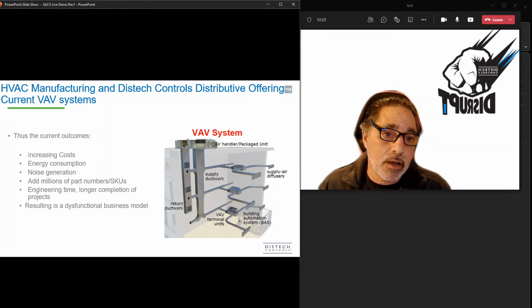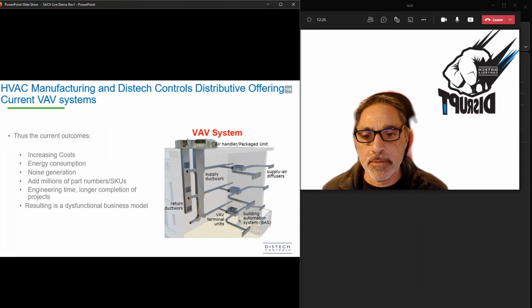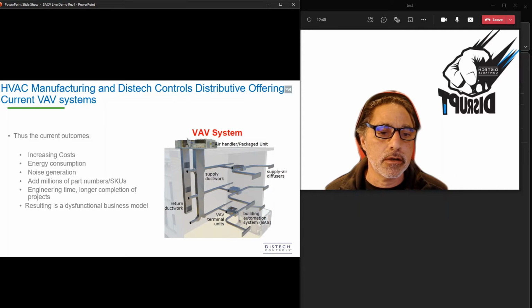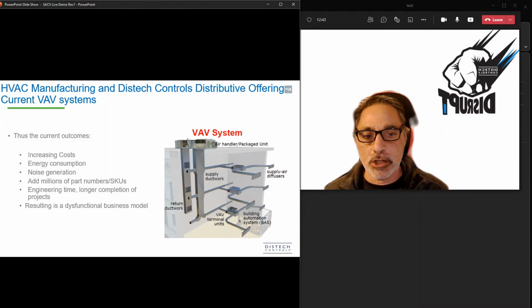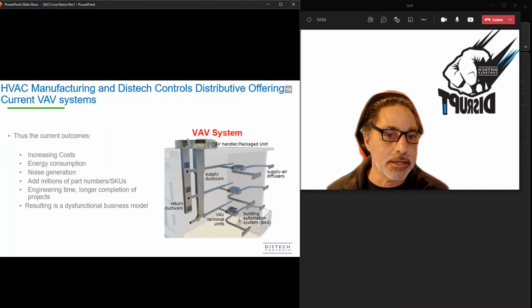And one thing that I haven't really mentioned even on the slide here: when you install a VAV system, what happens if a retrofit happens for that owner who wants to maybe move the walls around, change the design? What happens today is you almost have to redo your entire HVAC equipment design, change your ductwork based on the pressure. All of that gets changed. You have to go through and rebalance the system. With this new product, that's not the case anymore, and I will talk about that. And that's the terminology around flex spaces.